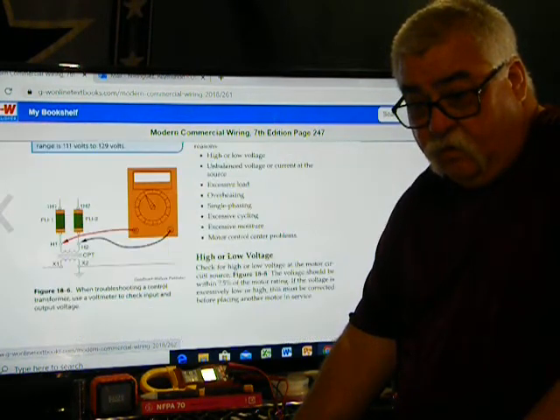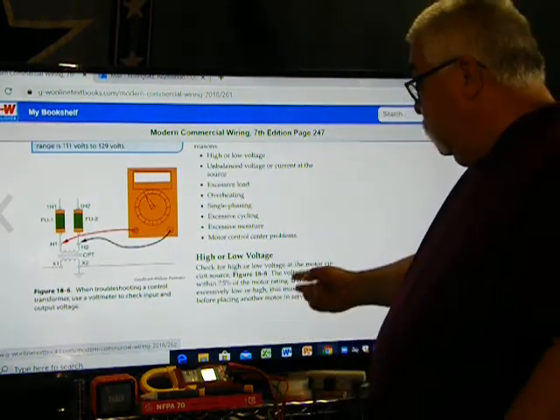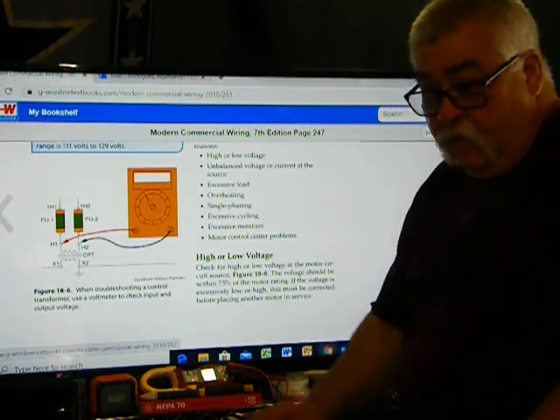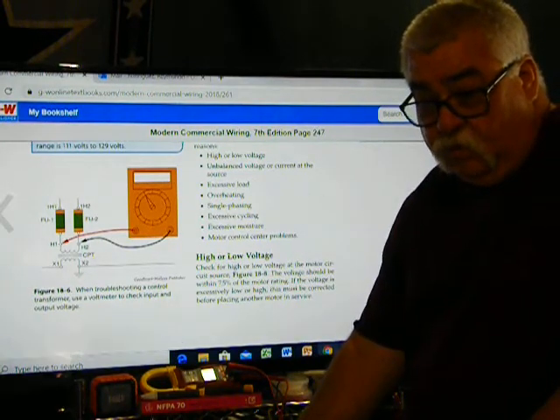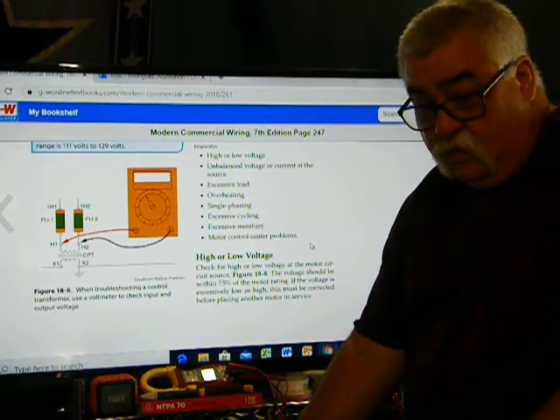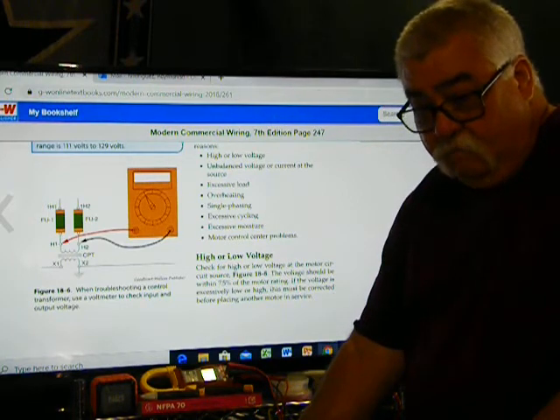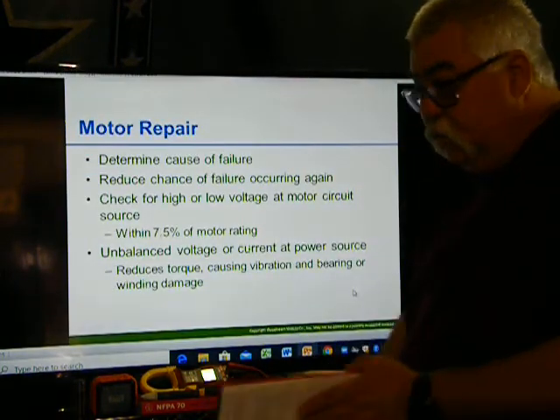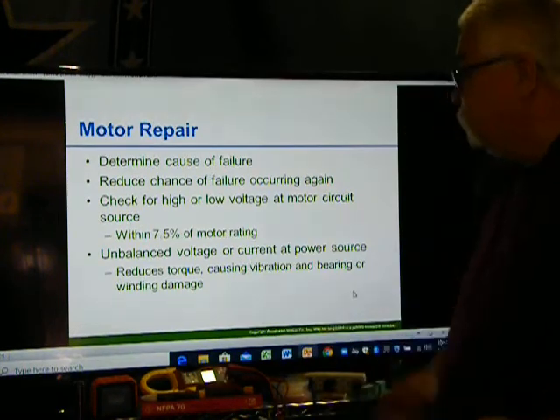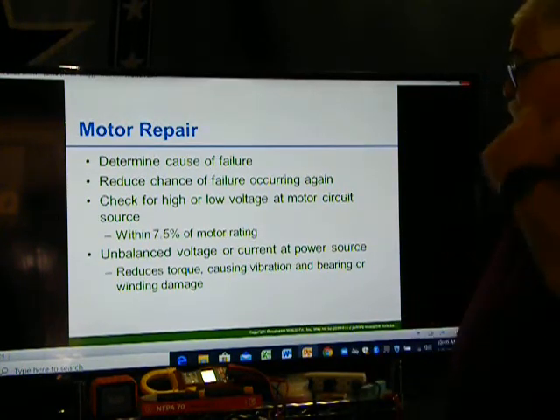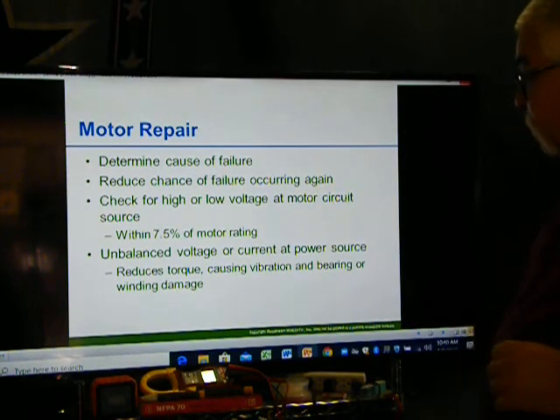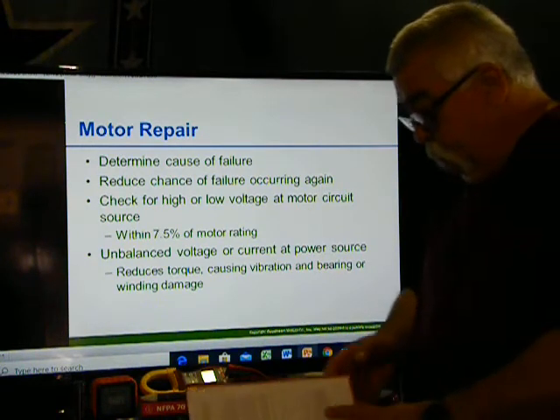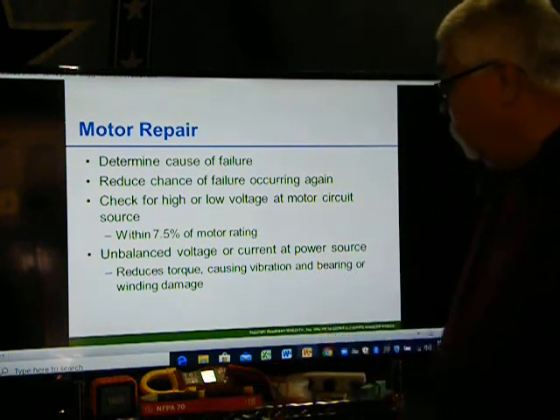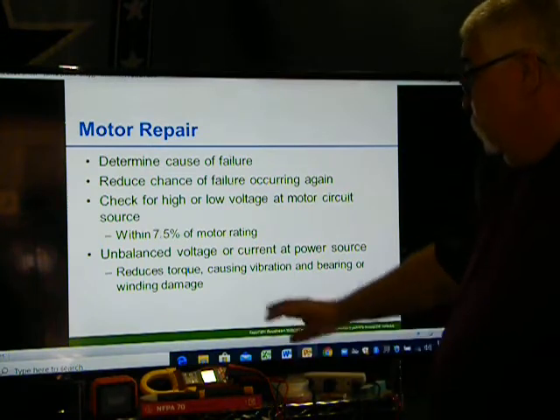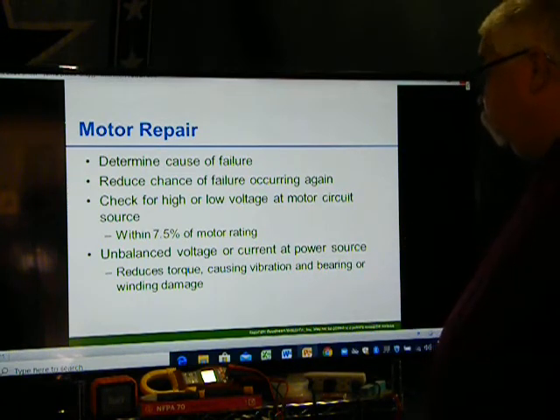So there's talking about the high voltage down here. It gives you all the different points and then explains each one. But on the PowerPoint, I got one sentence: check for high and low voltage at the motor source, and it has to be within 7.5% of the motor rating. Unbalanced voltage or current at the power source.